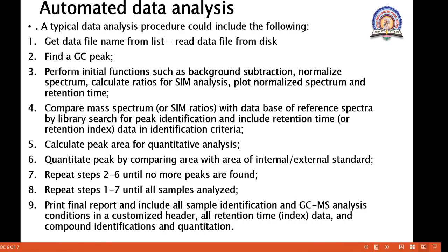Automated data analysis — the last point from this chapter. A typical data analysis procedure could include the following steps: get the data file name from the list, read the data file from disk, find the GC peak, then perform initial functions such as background subtraction, normalization, spectrum calculation, calculate the ratio for selected ion monitoring analysis, and plot the normalized spectrum and retention time.